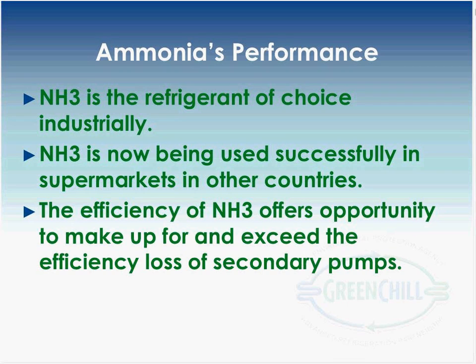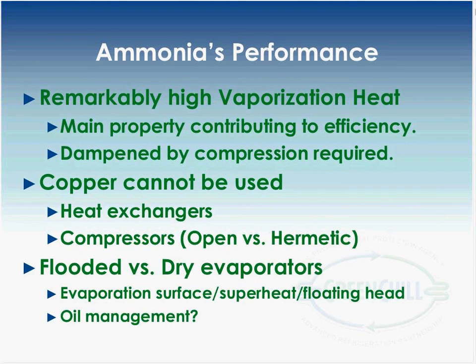This third bullet goes back to what I was talking about with the total equivalent warming impact. There's opportunity with using ammonia to make up for, and even exceed, some of the possible efficiency losses you see with secondary pumps. The next slide will hopefully get into one of the reasons why ammonia can be more efficient.